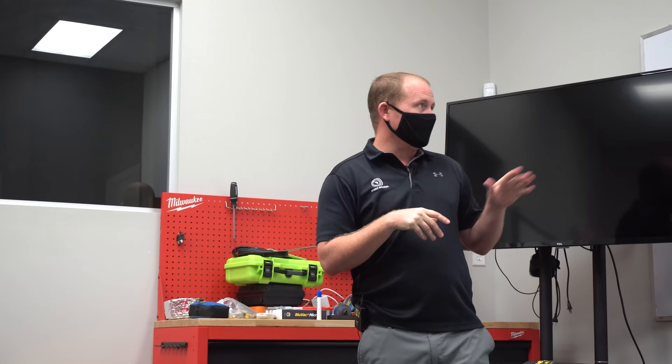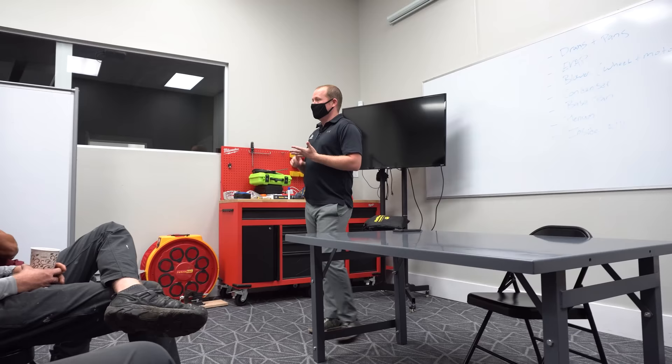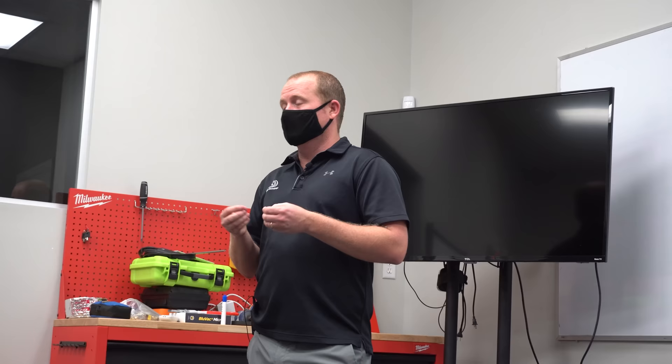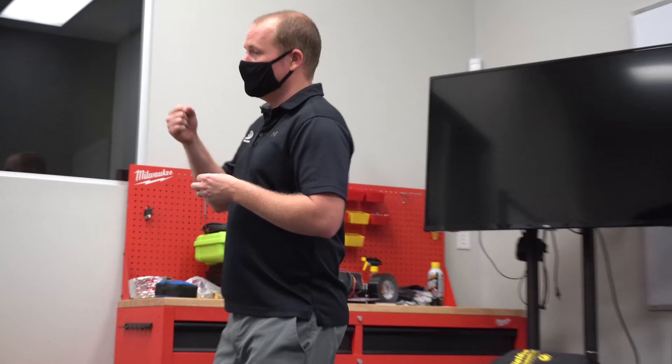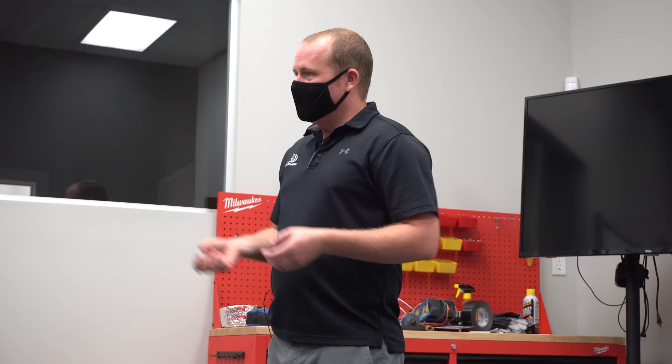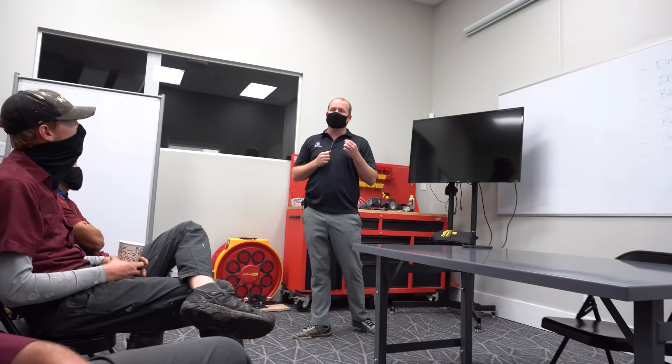So that's how we clean drains. When you have solid buildup inside a drain — which can happen — you can get various types of organisms, and some create a hard scale inside the drain, especially when the drain is allowed to dry out in the off-season. Sometimes the shop vac method won't work on the hard scale, which is why as a standard practice you should be looking down your clean-out to see what kind of stuff is in that drain. If it's gooey and slimy and washes away, good. But if it stays in there and it's hard, you'll want to use something more aggressive.